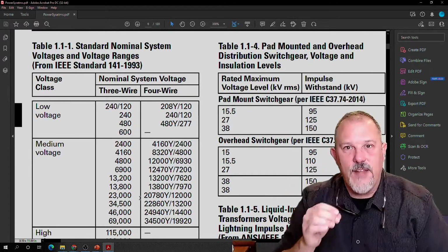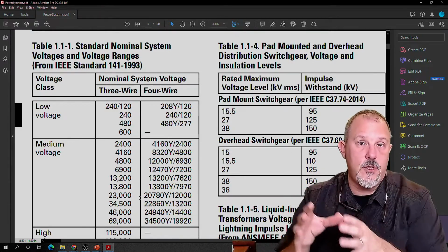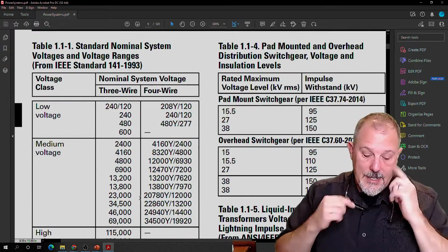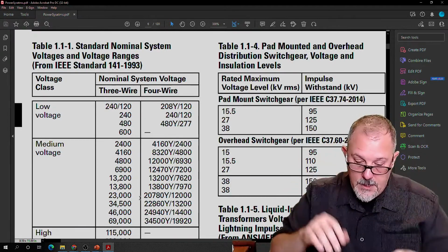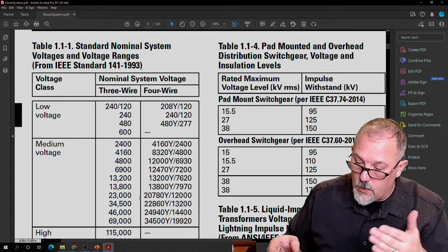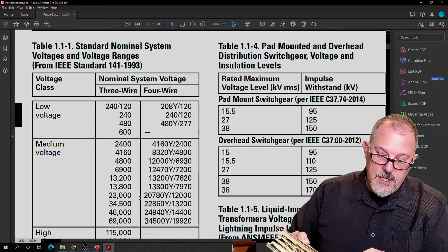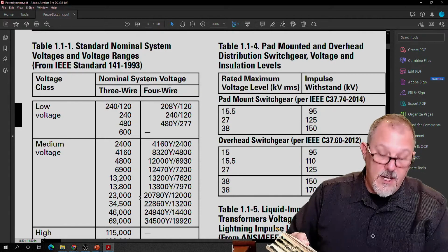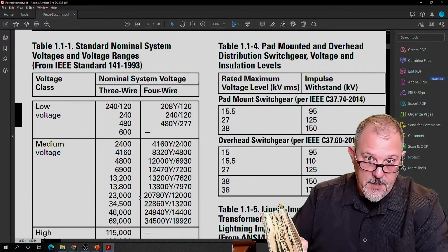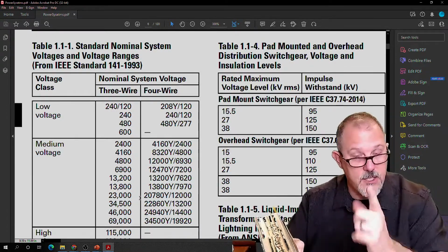The motor is the driving factor for when the equipment rated voltage is not equal to the nominal system voltage, something a little less. So in any case, I've worked on 2300 volt systems in the past. And then here, motors connected directly to the 13.8 kV bus would be rated 13,200 volts. So there's a good discussion in the Beeman handbook on voltage designations, and I think it's worth a read.